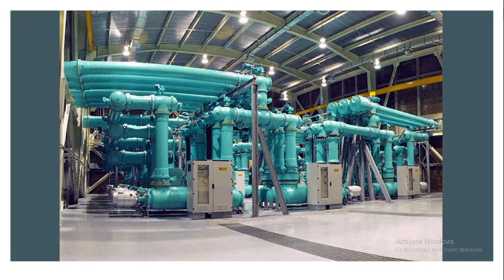So this is a pictorial representation of the gas insulated substation, which, as you can see, is housed in a building and placed on the floor. You can compare it with the normal substation you have visited, and compare the size over here. This is placed within the building, and this is the outermost surface of the building. All the equipment of the substation is housed within the building. Like this we reduce the size of the substation, and we will see the different parts in the further slides. This is just a pictorial representation of your gas insulated substation.